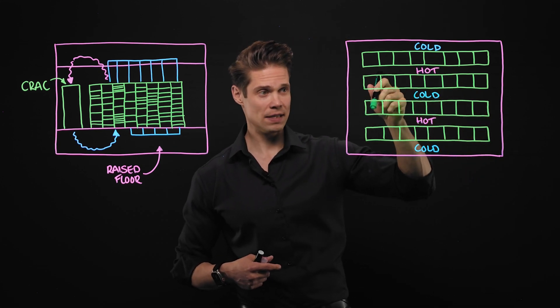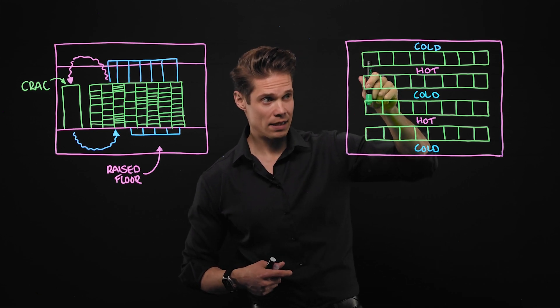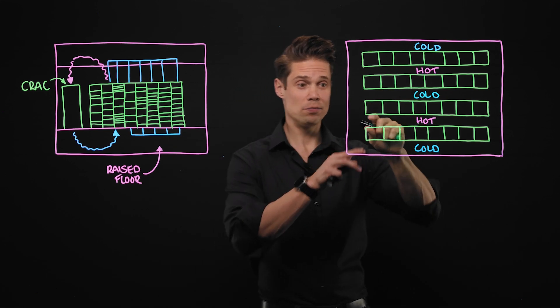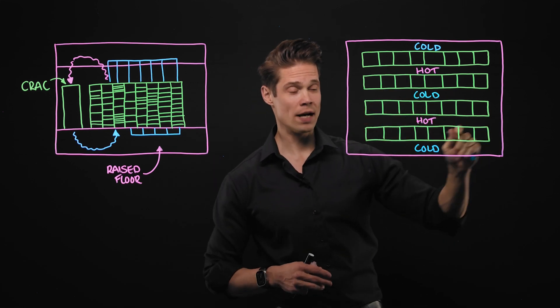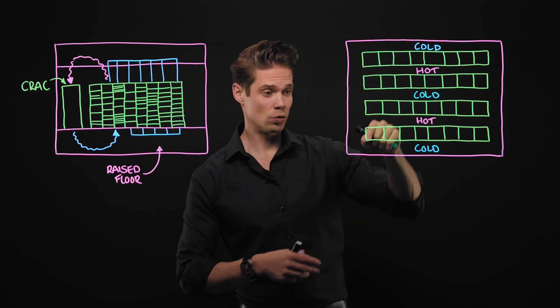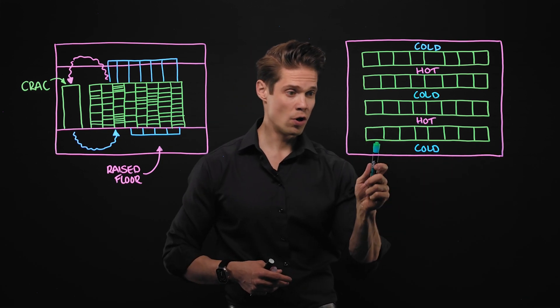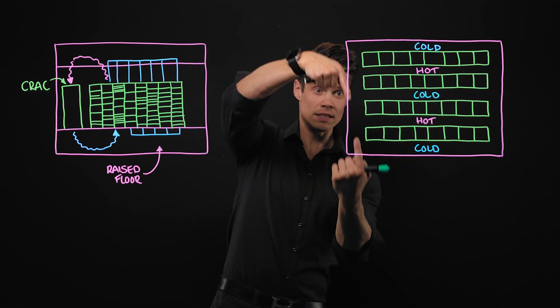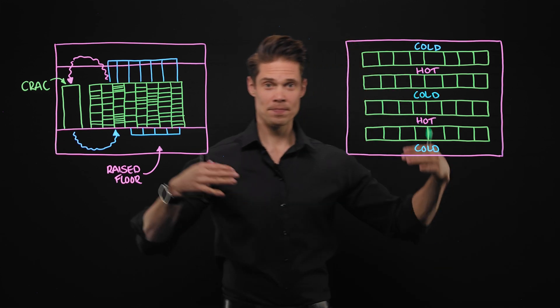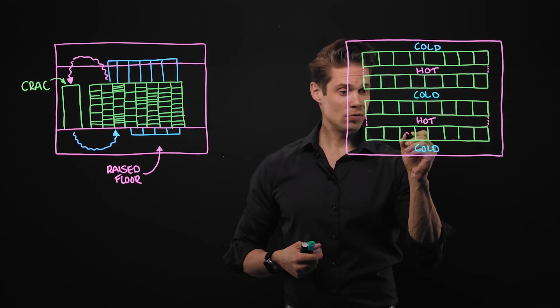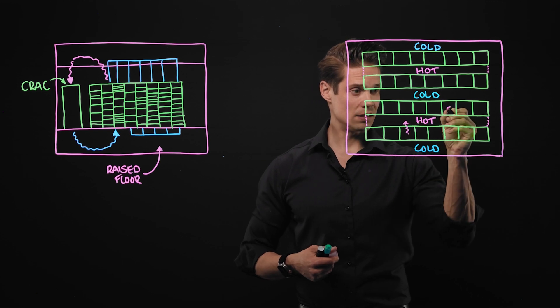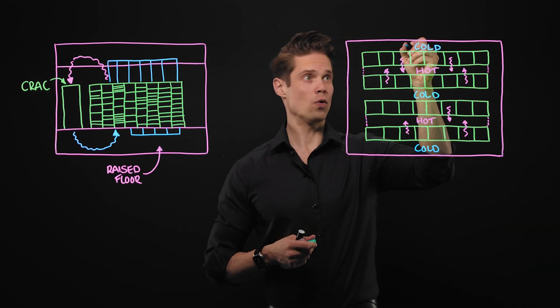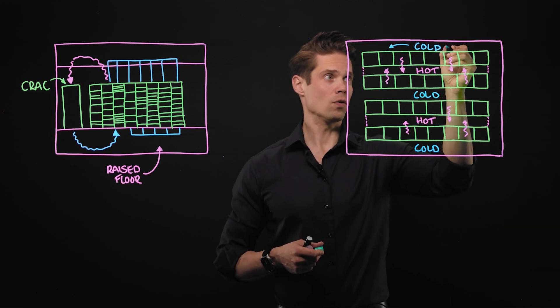So the hot air comes out from the back. So if we want this to be a hot aisle, then this row has to be facing the other way. So the front of the servers of this row would be here and the back on this side. So both of these rows are blowing their hot air on one aisle. The hot air comes out from these devices. And then the cold air comes out from the cold aisles.